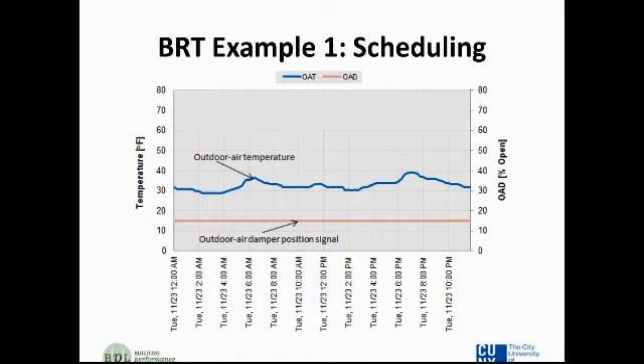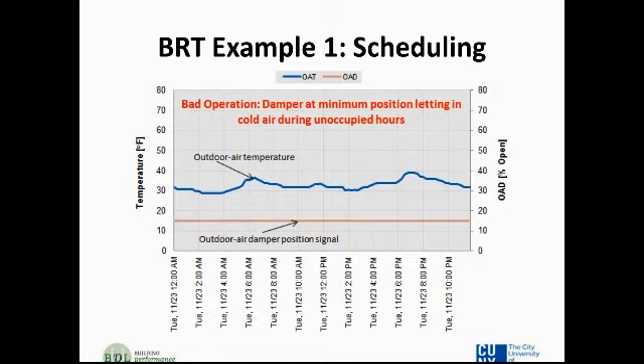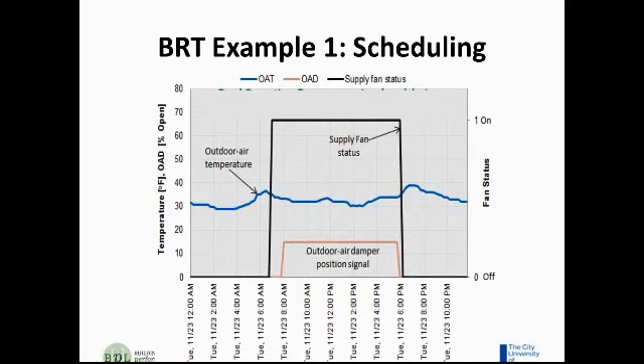Now, if this is a commercial building and there are no people in the building at night, it would be wise to close your outdoor air dampers at night. So that's an opportunity that we identify here. Operating at 15% open may actually be appropriate for the amount of ventilation that's typical for a minimum setting for ventilation. So it's probably good during operating hours, but then again, during off hours or unoccupied hours, we would want to drop that down. So we say that this is bad operation, the damper's at minimum position, letting in cold air during unoccupied hours.